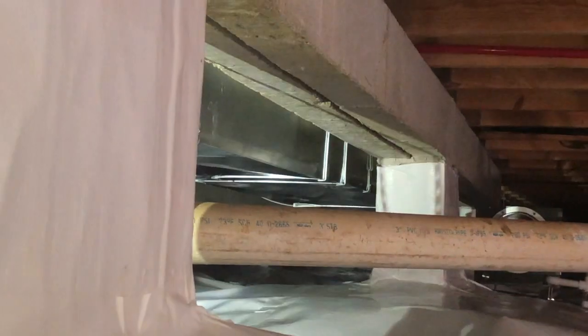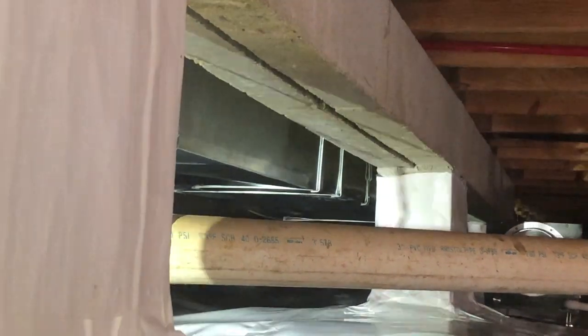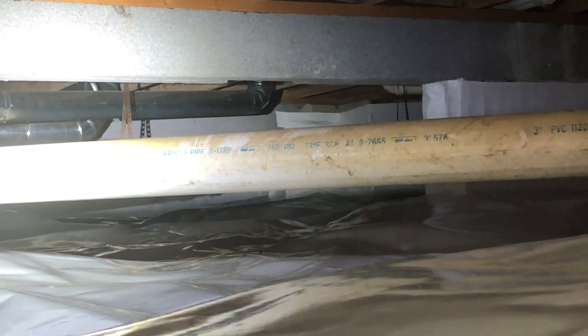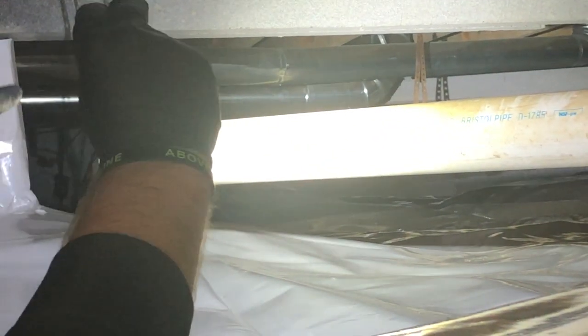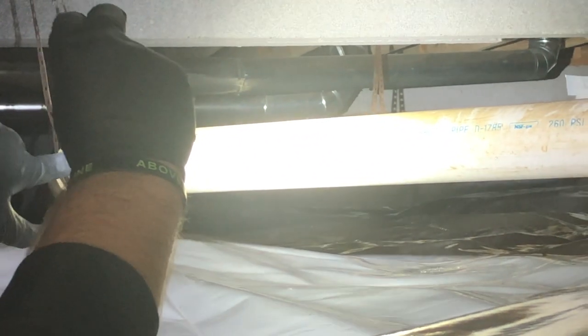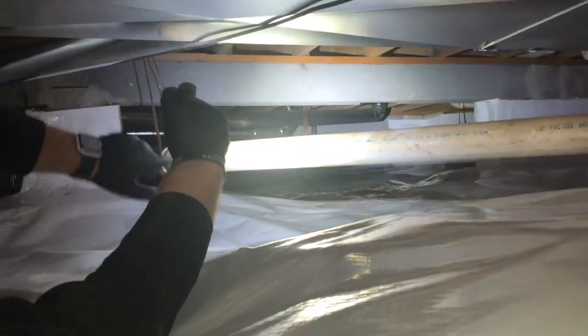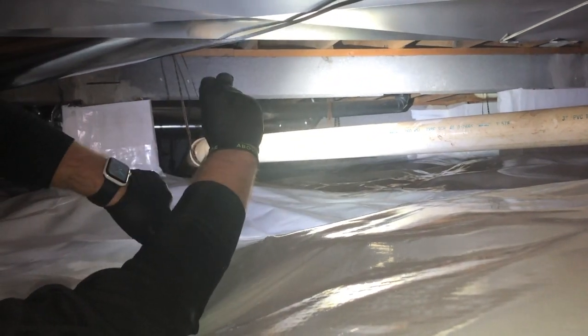So the supply trunk actually was about down to where our plumbing pipe is here, and that's where it stopped. Off of it, we had to run from that trunk there all the way over, as you can see, all the way to the other opposite side of the house, causing excessively long branch runs, which increased our TEL, our total equivalent length, and also killed our pressure and our velocity.